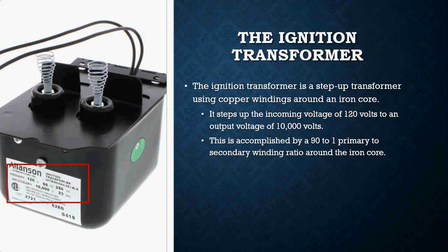The ignition transformer is nothing more than a step-up transformer that uses copper windings around an iron core. It takes 120 volts, supplied through these two black wires, which are our primary winding, and steps that voltage up to an output voltage of around 10,000 volts. That 10,000 volts comes out of these two springs right here. These two springs sit on the electrodes and send the spark down so that we can ignite the oil.